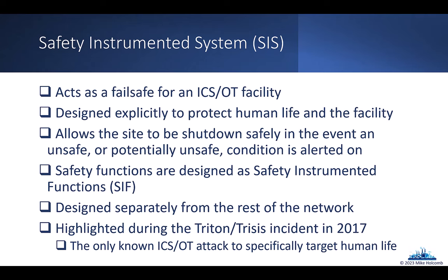But the idea with the SIS is that it monitors the entire plant. If there's ever a fault condition detected that could result in something bad happening, where maybe the plant breaks down and we have to take it offline to fix it, but most importantly, a condition that could lead to a type of explosion that would kill somebody, or a gas leak that could kill somebody. If it detects a fault that could lead to a dangerous situation, it can shut down part or the entire plant to keep it safe.